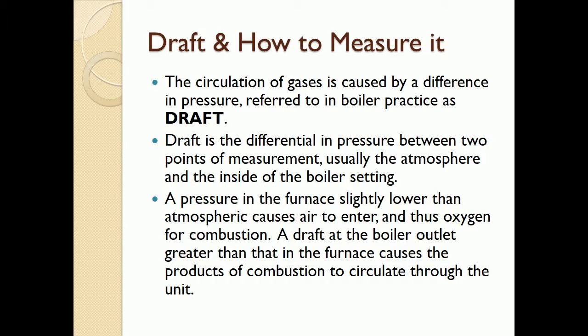A pressure in the furnace slightly lower than atmospheric causes air to enter, and thus oxygen for combustion. A draft at the boiler outlet greater than that in the furnace causes the products of combustion to circulate through the unit.